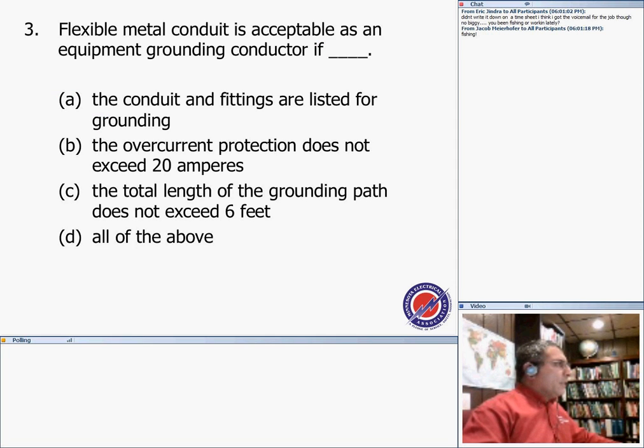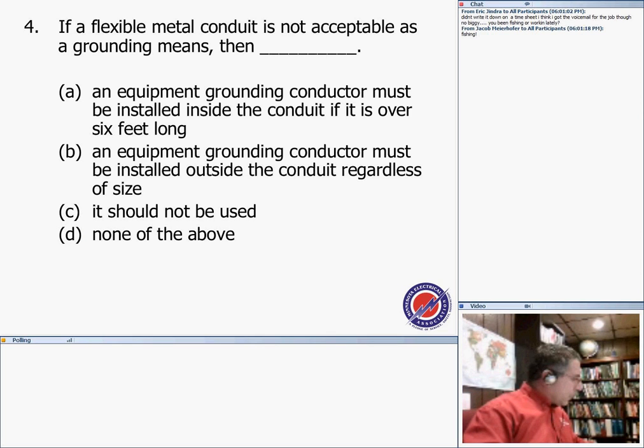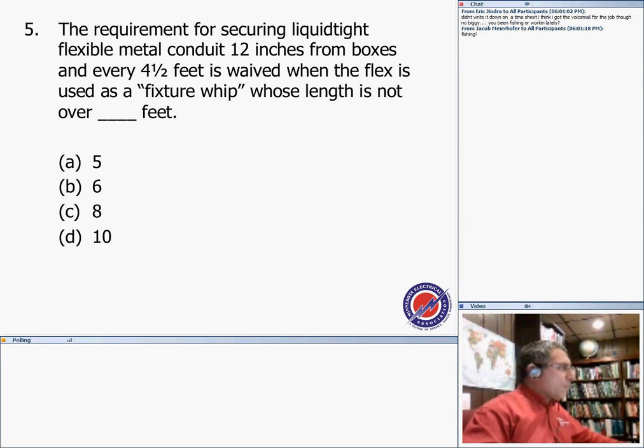The flexible metallic conduit is acceptable as the equipment grounding conductor. This is directly, guys, from the flex. If you go define the flex, first it has to be listed, with listed fittings, overcurrent device not exceeding 20, and there is a limitation on the length. So that's straightforward, no gimmicks. So all of you got it right. Moving into number 4: if flexible conduit is not acceptable as a grounding means, what shall you do? Of course, you have to install an equipment grounding conductor. It goes without discussion. All of you got it right.